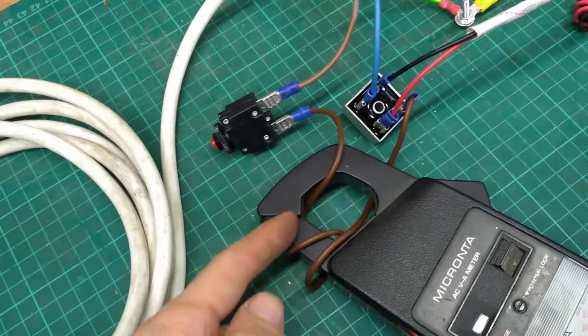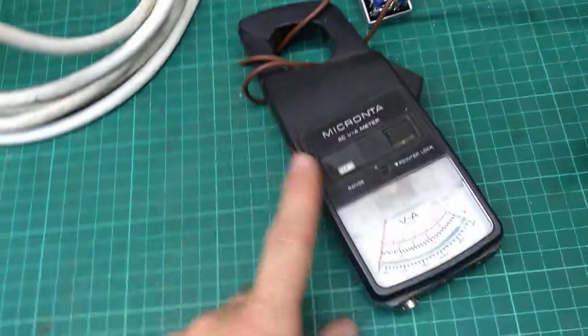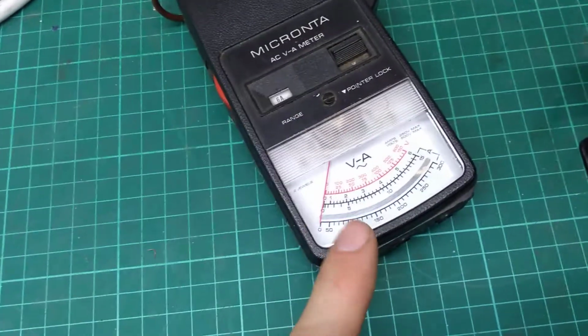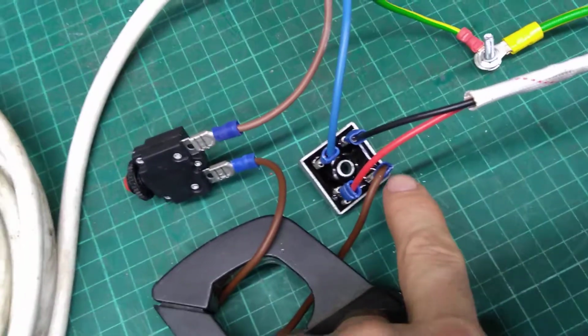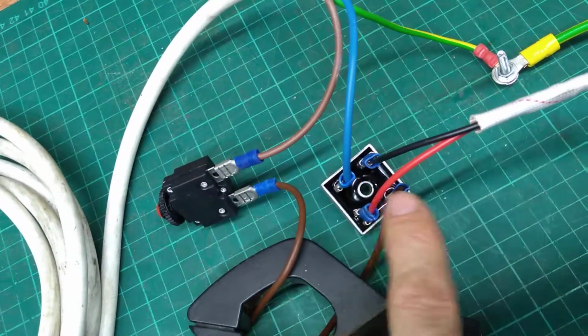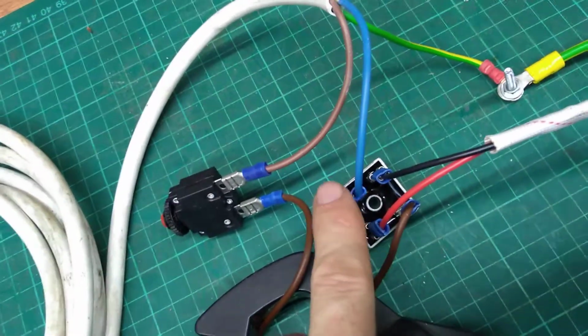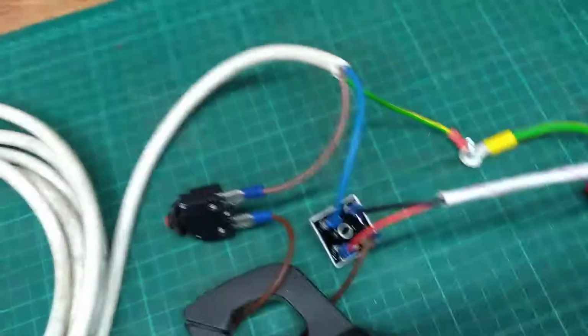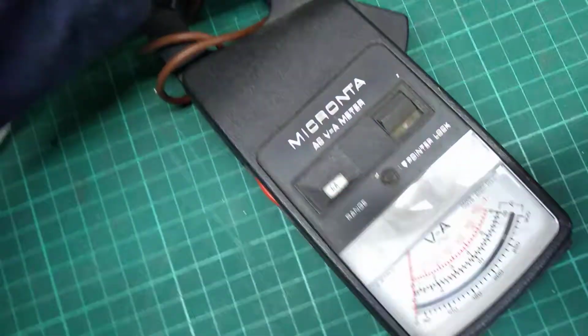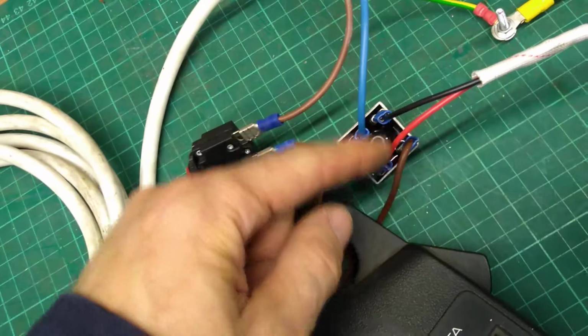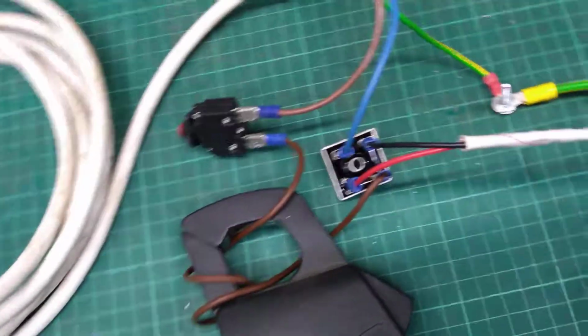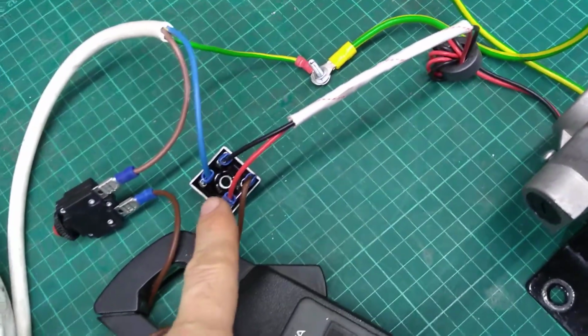Then I have just wrapped the live a couple of turns around the clamp meter just so I can make a non-invasive measurement of the current being drawn. Then we take the live to one of the two AC inputs here, so I take it to that one. Diagonally opposite, I take the neutral back to my site transformer. And then the other two diagonally opposite, I've got my positive supply and my negative supply, which then go to the motor. The protective earth, I put a strap onto the motor just in case anything amiss happens. For example, if the live were to touch one of the DC outputs, I think it's better to have a protective earth.